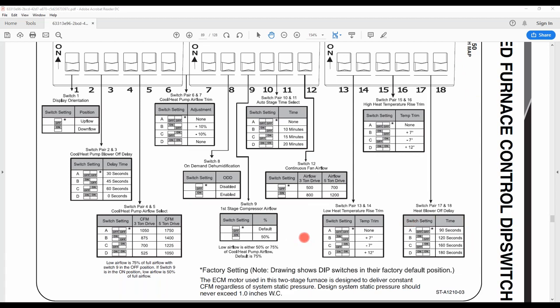So any questions on setting the dip switches for that 96 variable speed furnace? One thing to note, if you have questions, raise your hand. But one note is if you use the Econet thermostat, Econet takes over versus any dip switch settings. So the communicating Econet thermostat, when you install it, if you flip all the dip switches to on, Econet will ignore the dip switches and do as it is told and set up inside Econet.